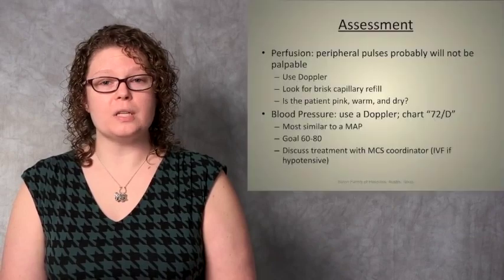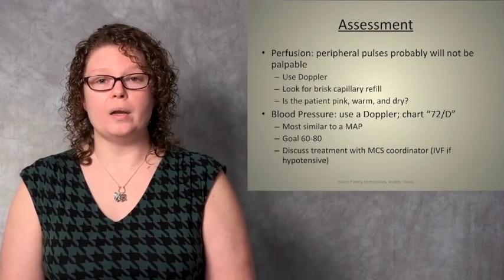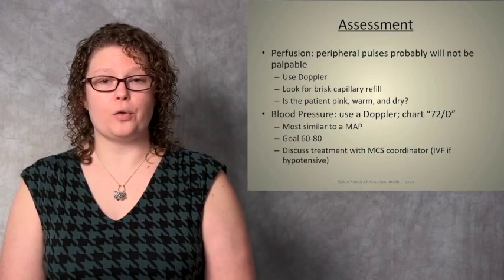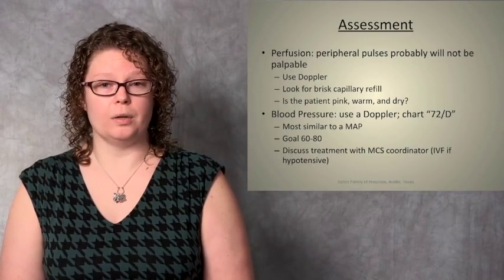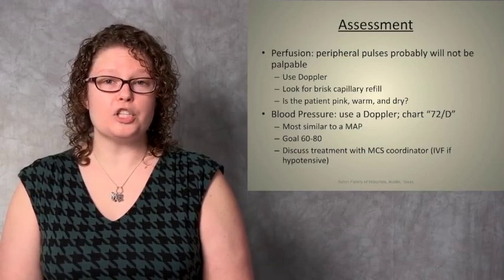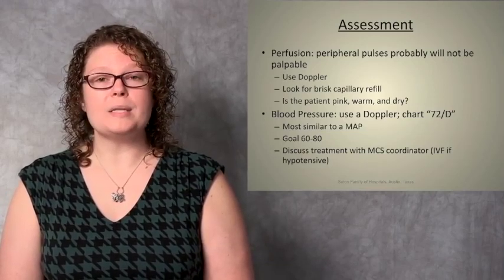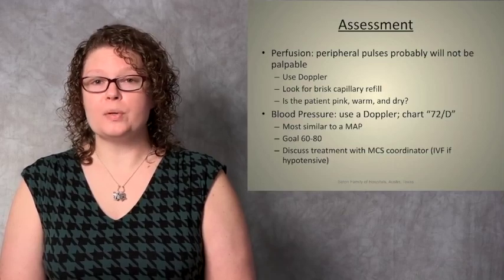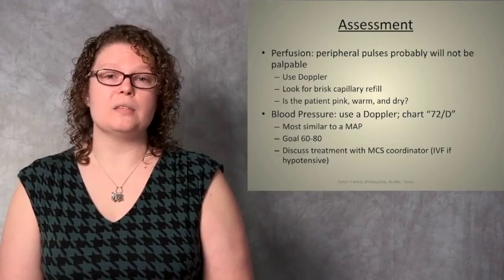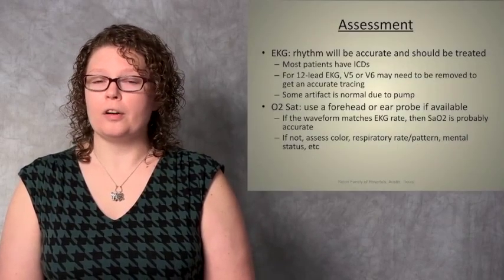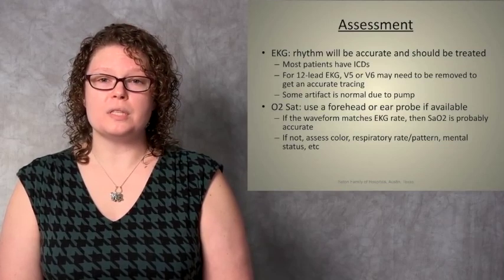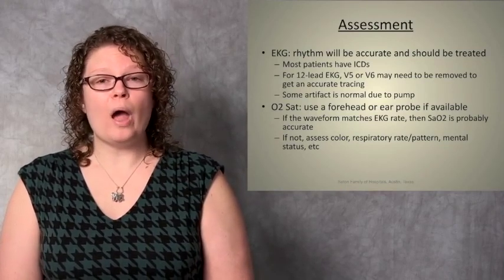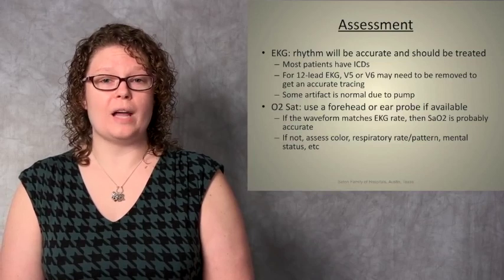Blood pressure is also different because of the continuous flow feature of the pump. We take blood pressure in these patients by using a Doppler, and you're only going to get one number, and that number is charted as, for example, 72/D for Doppler. The number that you get is most similar to a MAP, but it's not a true MAP, and our goal is 60 to 80. If these patients are hypotensive, they may need fluids, and if they're hypertensive, they may need treatment as well. Your EKG should read accurately. Sometimes there's some electrical artifact from the pump, but any arrhythmias that you see on your EKG should be treated. Know, however, that most of these patients do have fully functional ICDs.